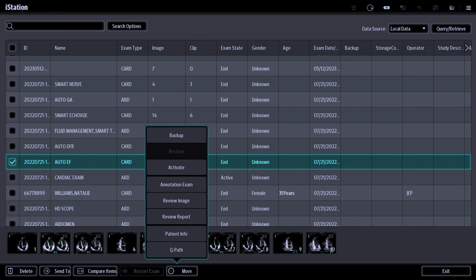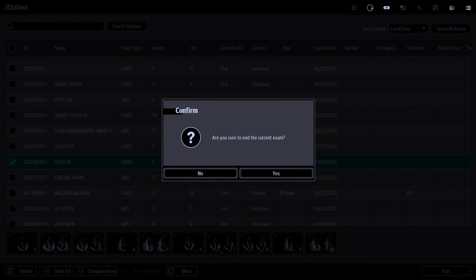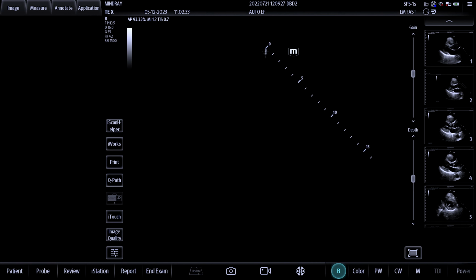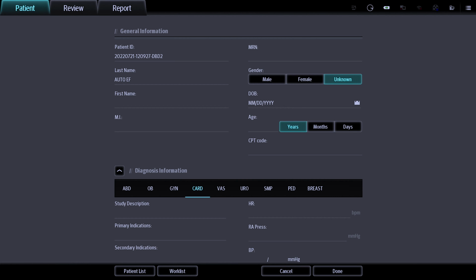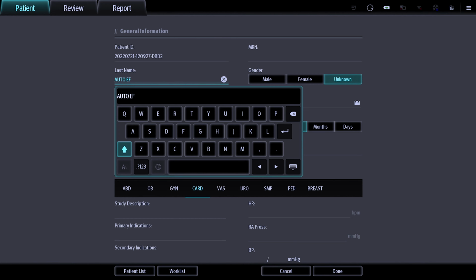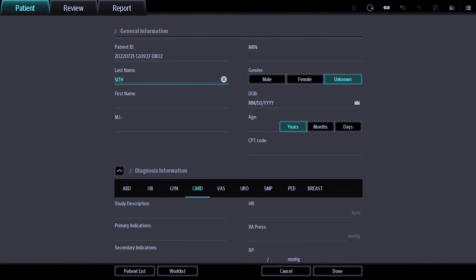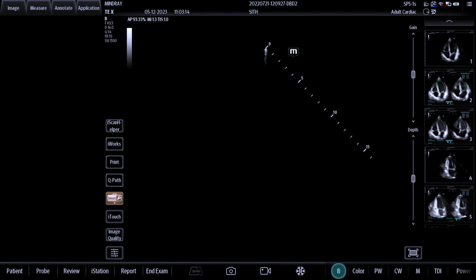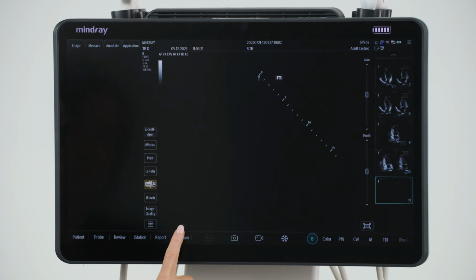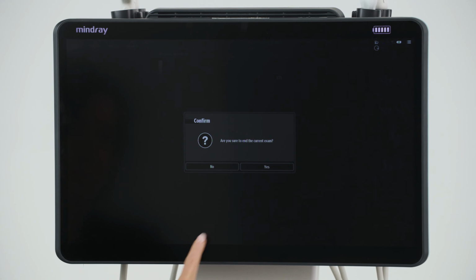Select the More button at the bottom of the screen. Available options will be illuminated. Select Activate. Navigate to the Patient tab to change demographic information. To update, tap on the desired field and an X will appear. Select the X to clear this field. Enter corrected patient information at this time. Select Done to accept changes. Remember to end your exam again once desired changes have been made.